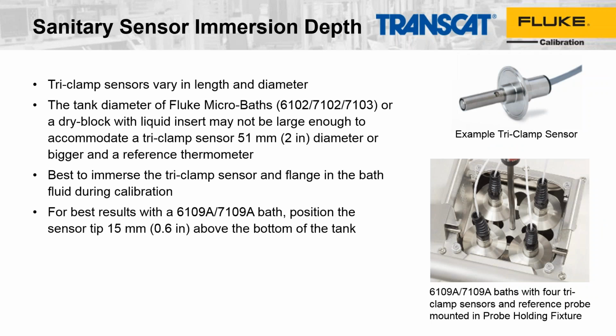These tri-clamp sensors that we're showing have 2-inch flanges, I believe, if I remember correctly. And I need to back up a little bit. What we want to talk about really quickly here is the importance of immersion depth. We mentioned this earlier, and these sensors are often just like the one shown here, where they have short sensors because they have to plug into a pipe, and then they'll have a flange. So we wanted to make sure that the tank was big enough that the entire assembly could be lowered down into the fluid, so that you're not getting heat loss or stem effect because of the flange being at room temperature and the temperature sensor down inside the bath.